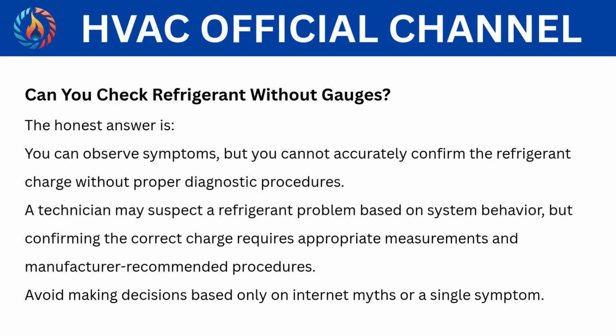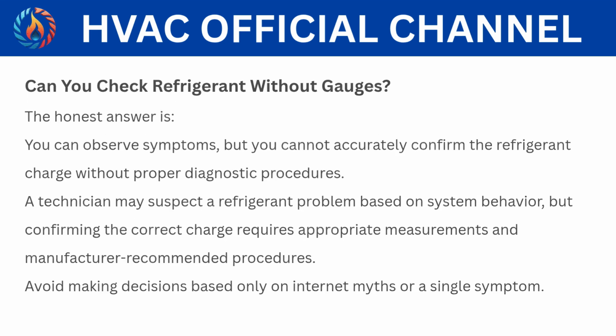Can you check refrigerant without gauges? The honest answer is, you can observe symptoms, but you cannot accurately confirm the refrigerant charge without proper diagnostic procedures. A technician may suspect a refrigerant problem based on system behavior, but confirming the correct charge requires appropriate measurements and manufacturer-recommended procedures. Avoid making decisions based only on internet myths or a single symptom.